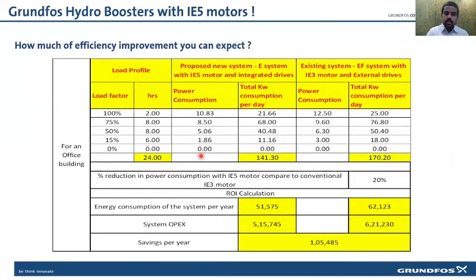And moving on, a small explanation about how much we can expect in terms of energy saving, a small comparison from live site data. So this is an existing IE3 motor with an external drive system, where the energy consumption for various load patterns, from 100 to 0%, is 170 kilowatt hour per day. For the same profile, if you switch over to IE5 motors with integrated drives, we can have an energy reduction close to 20%, and we can have a saving close to 1 lakh rupees when compared with IE3 motors, which we are using conventionally in today's market. So this is just a perspective on how much we can expect in terms of energy saving by just switching a motor from IE3 external drives to IE5 permanent magnet motor technology.